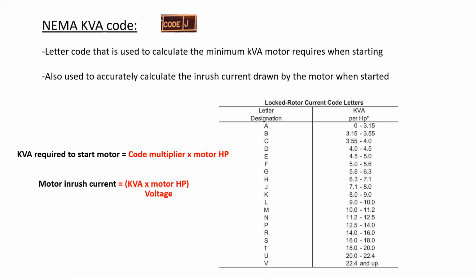A NEMA table is a table provided by manufacturers. It's not located in the code book, and it is not a table that you would have to memorize. Instead, if given the table, we need to know what to do with it. If I want to know the KVA required to start the motor, I take the code multiplier, so J in this case gives me a range of 7.1 to 8, and I multiply it by the motor's horsepower. Typically, people will utilize the upper end.